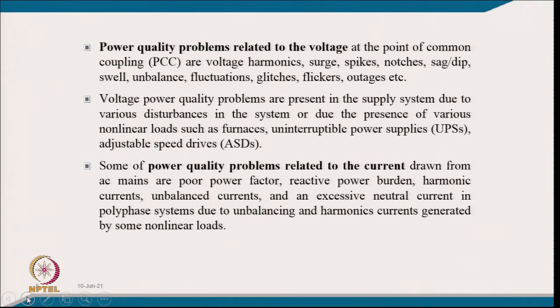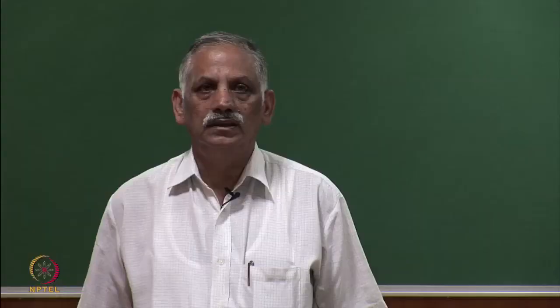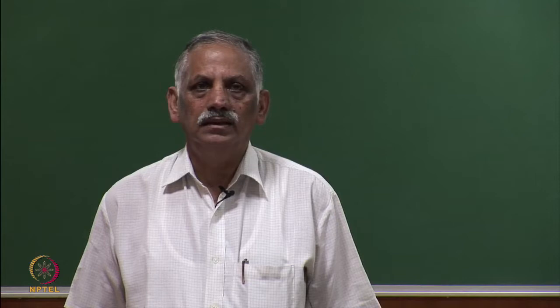Some power quality problems related to current drawn from the AC mains are poor power factor, which causes burden on the distribution system as well as transformer feeders and equipment, reactive power burden, harmonic currents in addition to fundamental current, unbalanced current quantifiable as negative sequence current, and excessive neutral current in polyphase systems, especially 4-wire distribution systems.